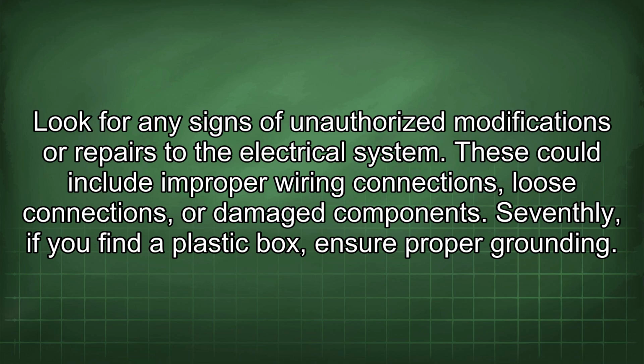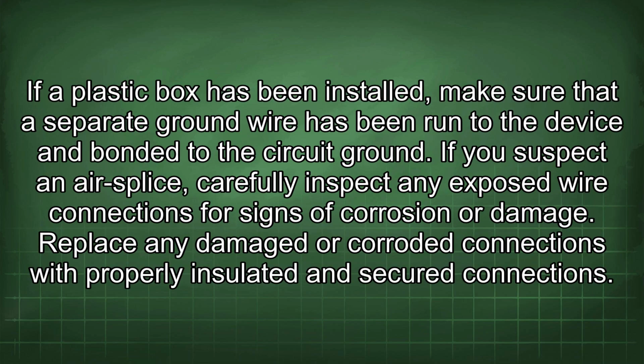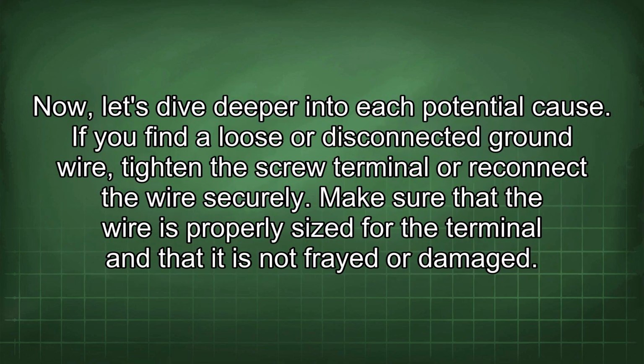Seventhly, if you find a plastic box, ensure proper grounding. If a plastic box has been installed, make sure that a separate ground wire has been run to the device and bonded to the circuit ground. If you suspect an air splice, carefully inspect any exposed wire connections for signs of corrosion or damage. Replace any damaged or corroded connections with properly insulated and secured connections. Now let's dive deeper into each potential cause.